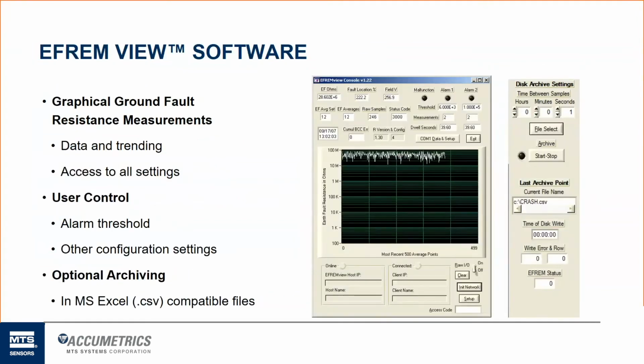So here's an example of what the EFREM View software would look like. It offers a graph of what the resistance trend plot will look like over time. It's going to appear as a scatter, because it's not able to measure accurately any resistance values over 500 kilohm. It's just going to look like a massive open circuit, toggling between, in this case, about 10 megohm and 100 megohm.